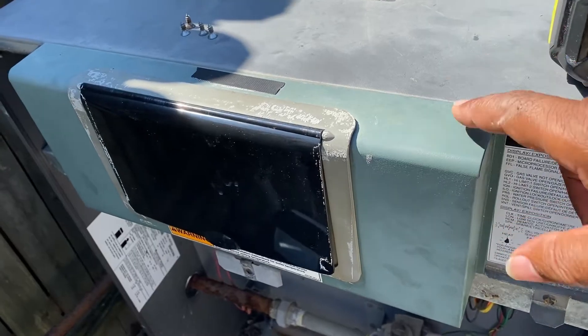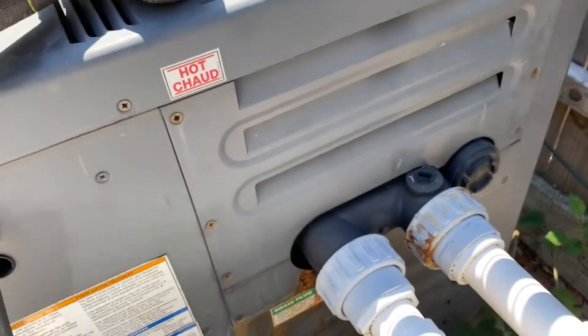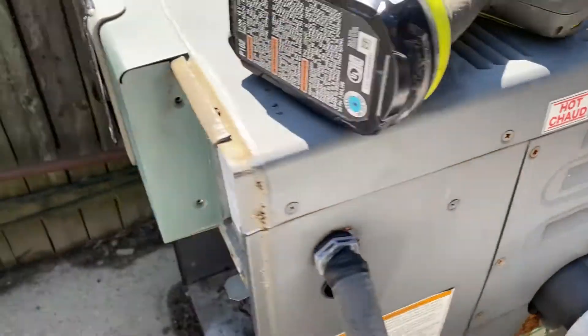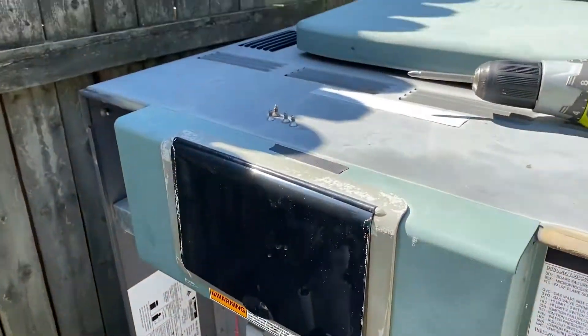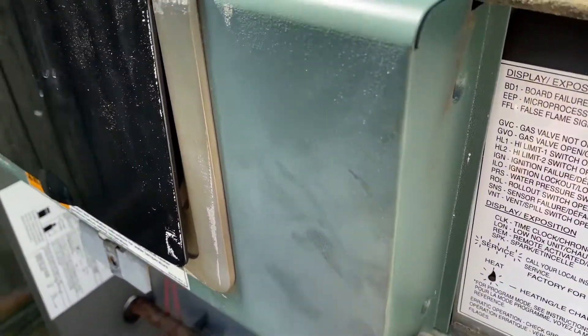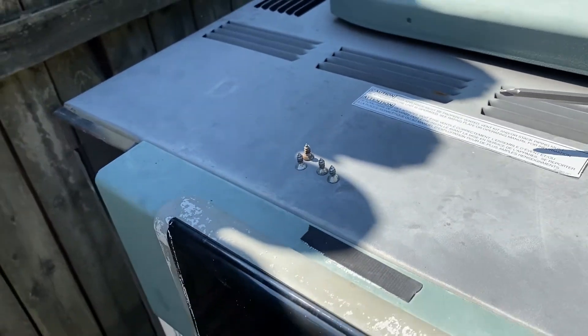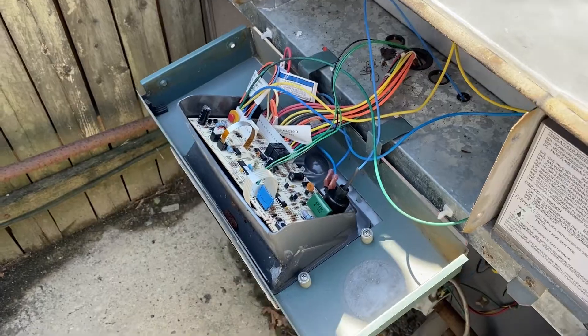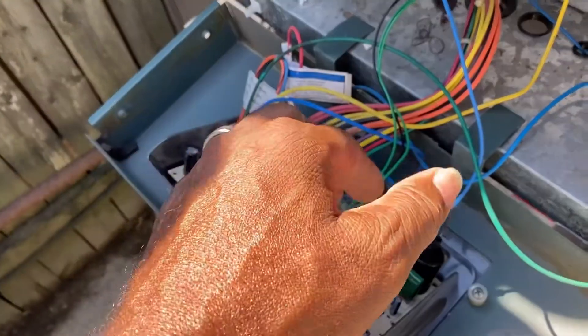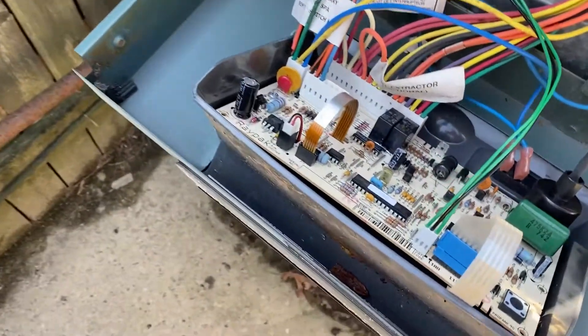To get at the circuit board that the thermistor temperature sensor is set to, take off this plate, take off the front cover of the heater, which reveals the four screws that hold this in place. This whole thing drops down — and there are the four screws. It drops down, revealing the back of the circuit board, and the thermistor sensor is connected right here to that connector.